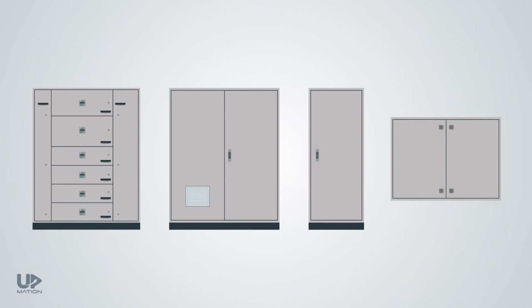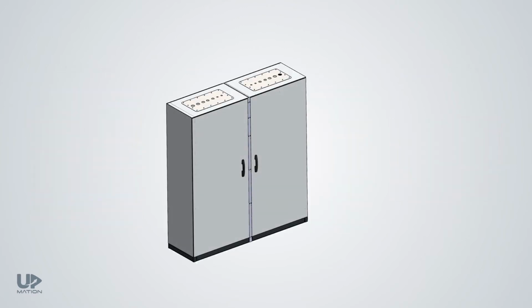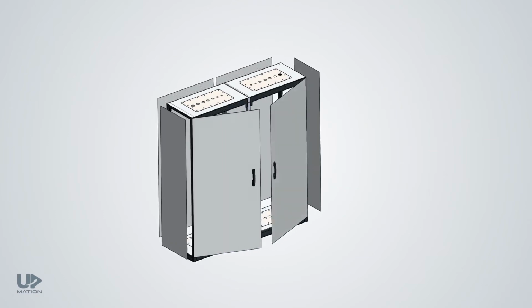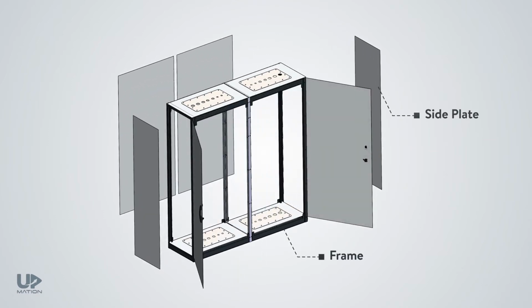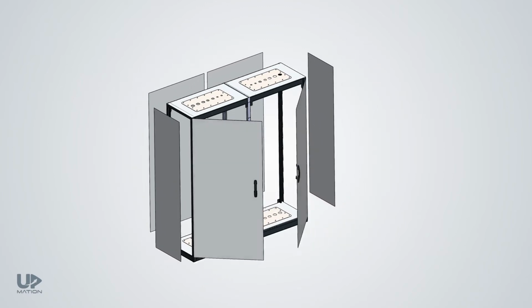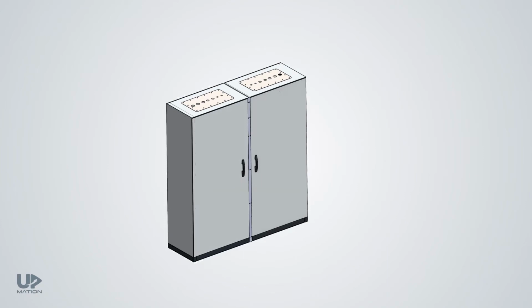Obviously, the more electrical components we have to install inside the panel, the bigger the size of the electrical panel should be. In addition to the number of the components, the purpose of usage can also impact the size, type, and configuration of the enclosure. Generally, an electrical panel enclosure is comprised of a chassis or frame and some plates on its different sides that can be dismantled and assembled pretty easily to provide different configurations known as enclosure baying systems.